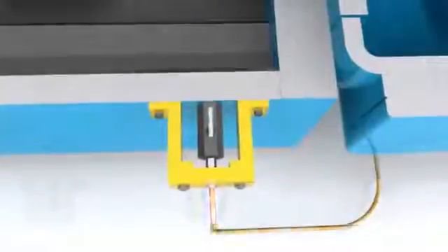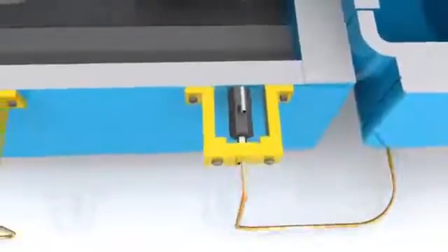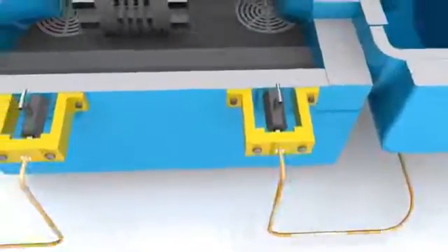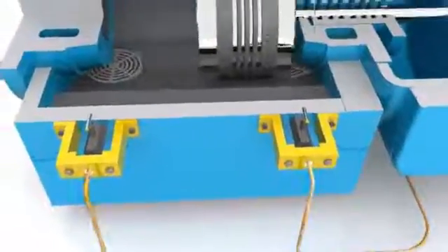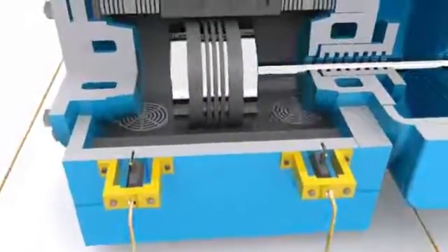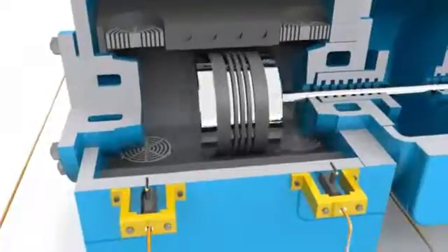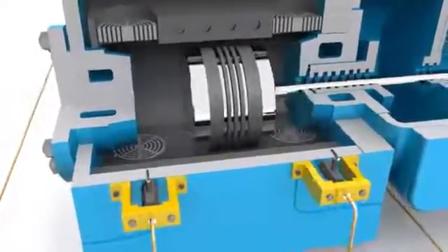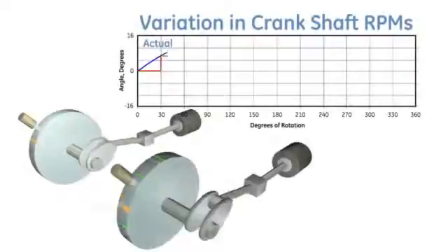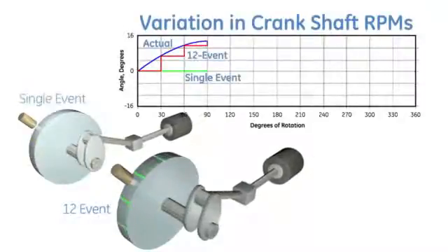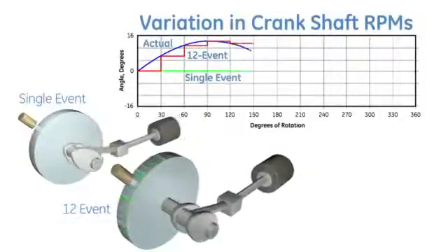monitoring capabilities. It starts with robust transducers that are permanently mounted on each cylinder. This eliminates the need to continually connect and disconnect the sensor every time a measurement is needed. Our patented Bentley Nevada cylinder pressure transducer can endure 24/7 exposure to the extreme conditions within the compressor. It provides accurate, continuous, and dynamic pressure data to our recip cylinder pressure monitor, even when the machine is in distress. Essential to a complete cylinder pressure profile is the ability to correlate cylinder pressure with crank angle location.